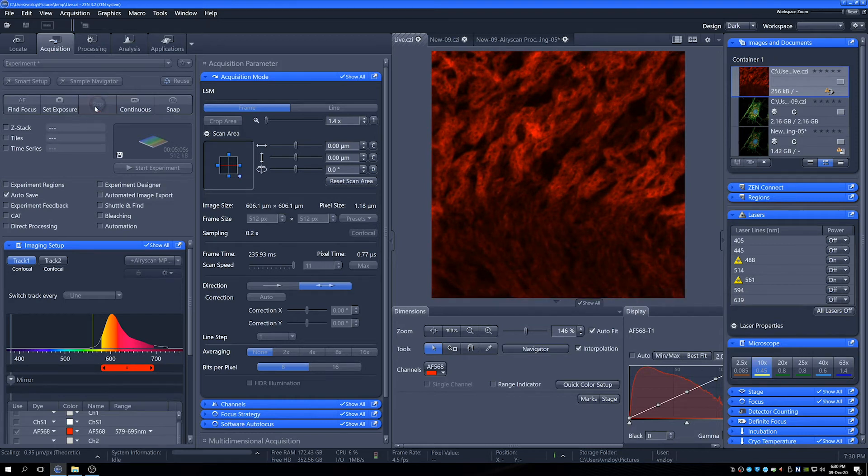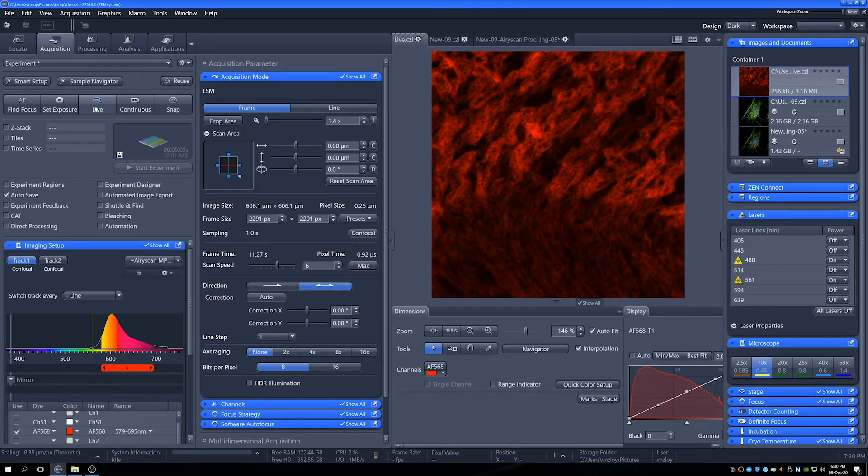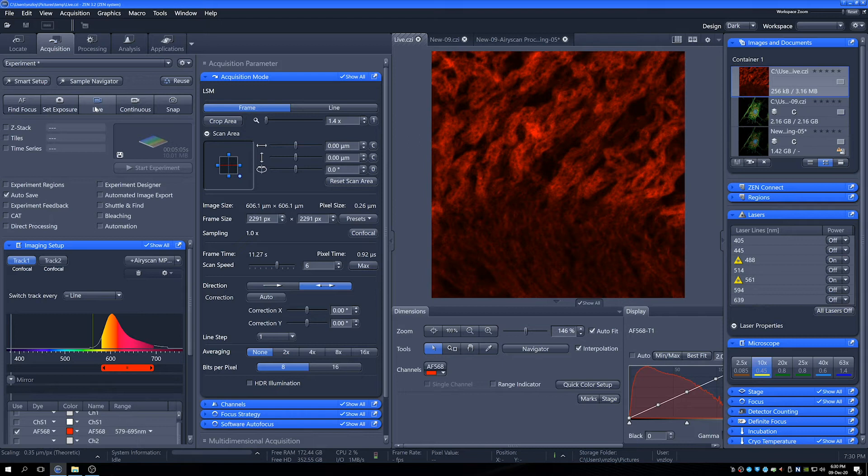Do you start from live or from continuous? I would always start from live and the reason I would do that is the live is set to give you a 512 by 512 area as fast as the scanner can scan in a single color. So it's very good for finding focus very quickly. And it's very good if you want to be able to move around and have a little look at where you are because the refresh rate is very quick.